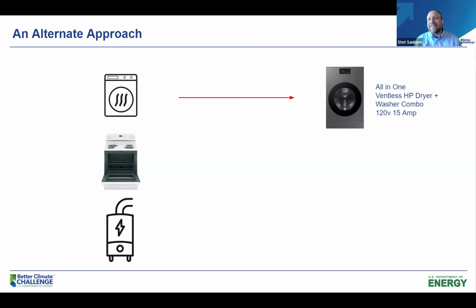I got my parents to install one, which, trust me, getting my parents to do anything takes an act of God. But this new generation of equipment, and they're especially valuable for apartments, are these all-in-one washer-dryer combos with a heat pump component. So the dryer is heat pump based, but it's an all-in-one space-saving ventless design. There's at least 3 manufacturers now that have these out on the market. But the key thing of why I bring it up is, in lieu of bringing a dedicated circuit to that space, these can plug into a standard 120 volt, 15 amp circuit. So these can go into a standard outlet. They don't necessarily need a dedicated 240 volt circuit brought into the space.